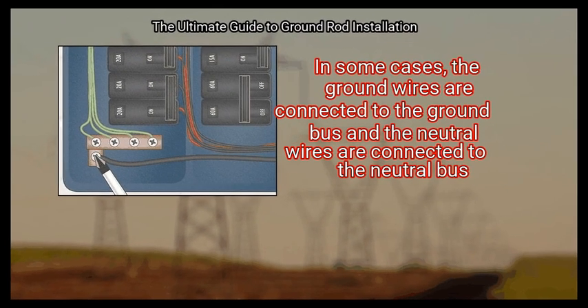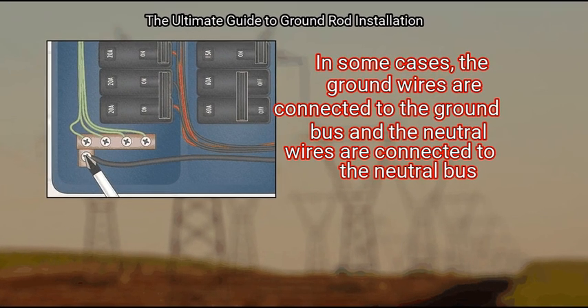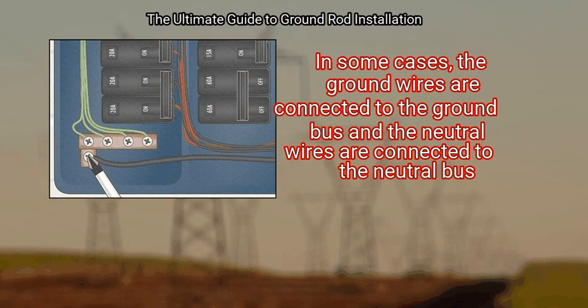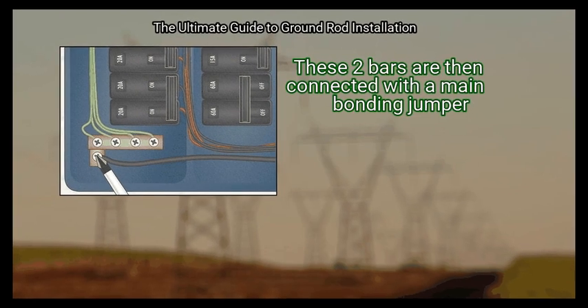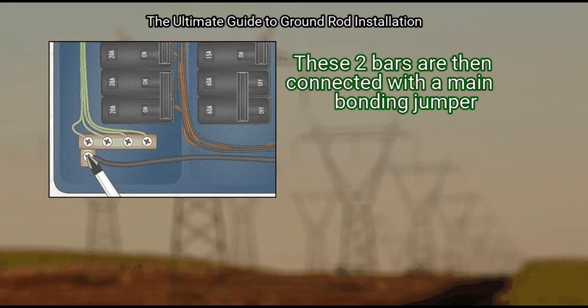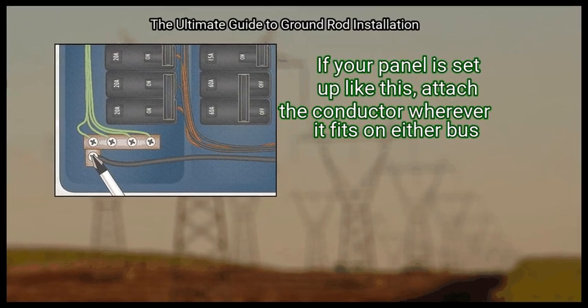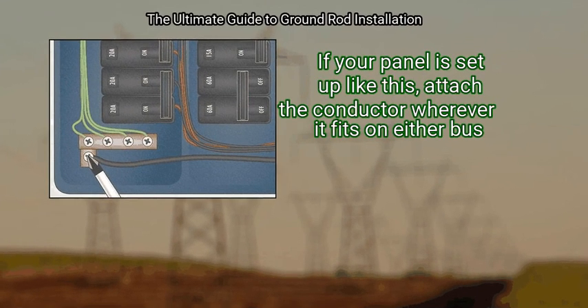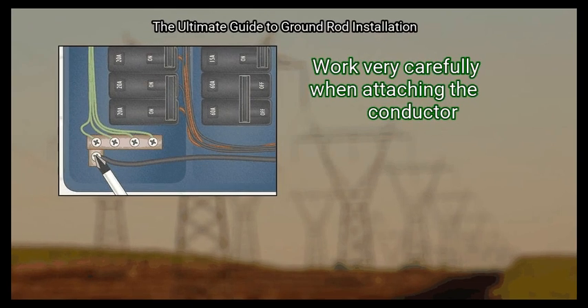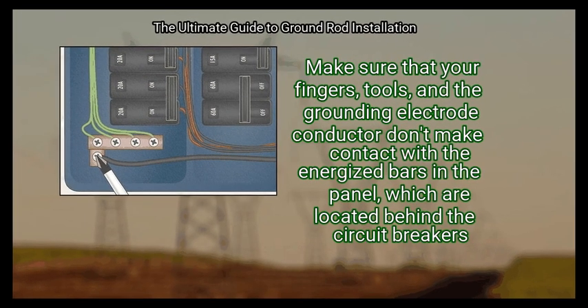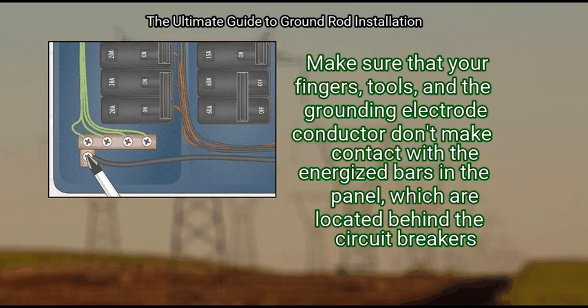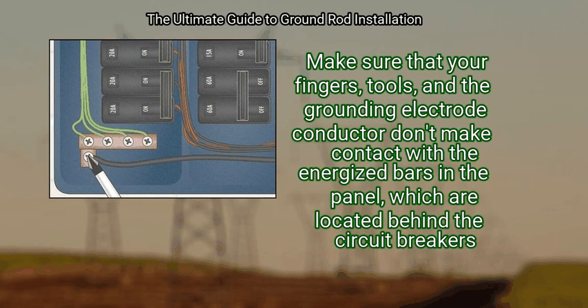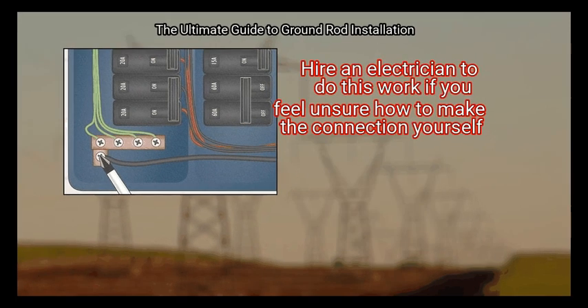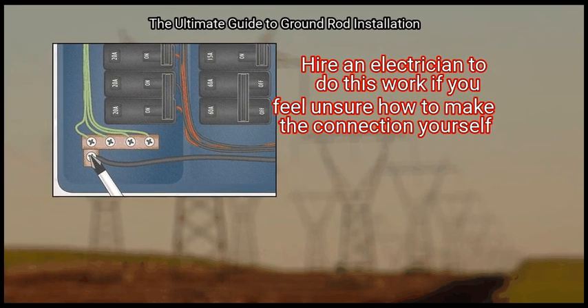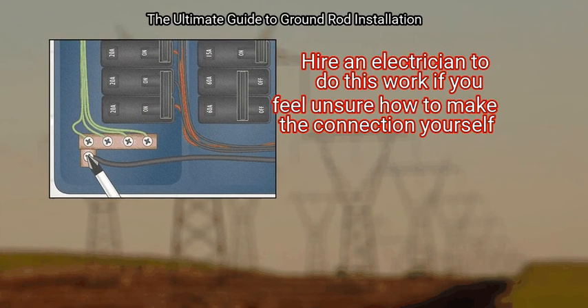In some cases, the ground wires are connected to the ground bus and the neutral wires are connected to the neutral bus. These two bars are then connected with a main bonding jumper. If your panel is set up like this, attach the conductor wherever it fits on either bus. Work very carefully when attaching the conductor. Make sure that your fingers, tools, and the grounding electrode conductor don't make contact with the energized bars in the panel, which are located behind the circuit breakers. Hire an electrician to do this work if you feel unsure how to make the connection yourself.